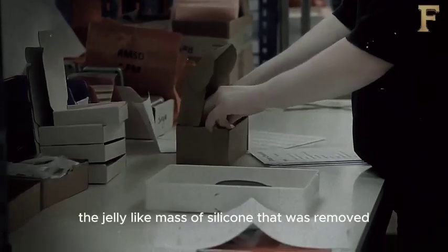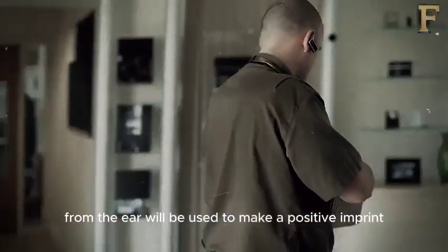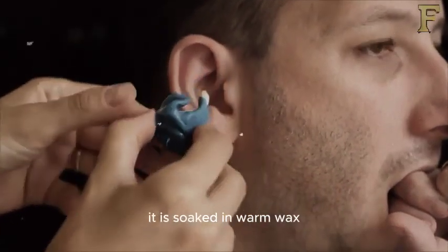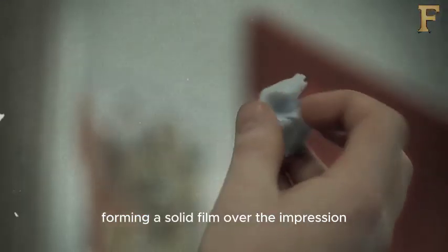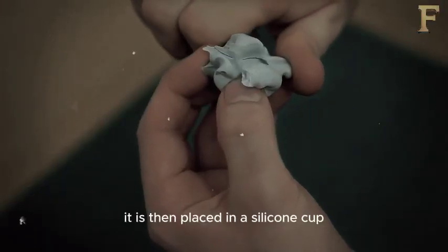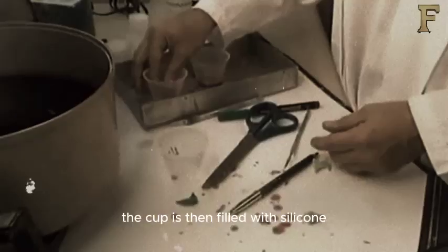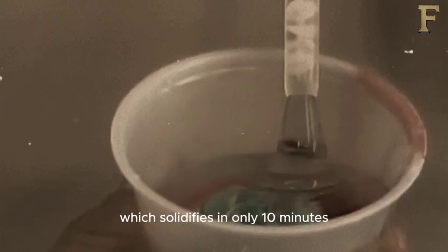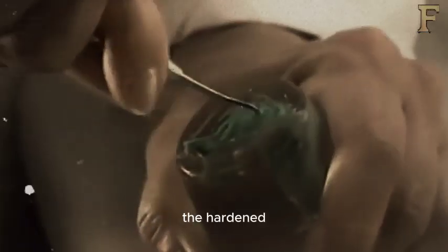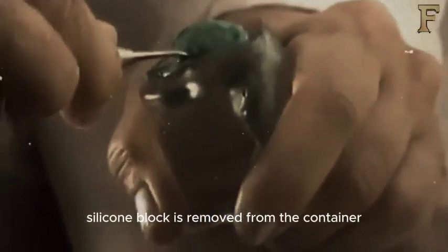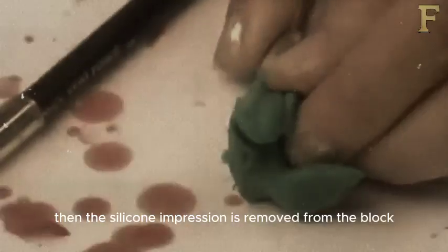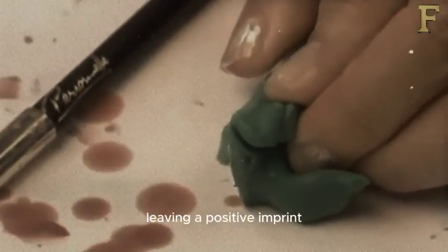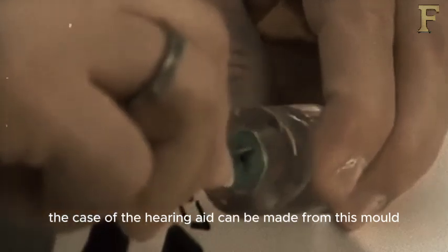The jelly-like mass of silicone that was removed from the ear will be used to make a positive imprint. It is soaked in warm wax, forming a solid film over the impression. It is then placed in a silicone cup. The cup is then filled with silicone, which solidifies in only 10 minutes. The hardened silicone block is removed from the container. Then the silicone impression is removed from the block, leaving a positive imprint. The case of the hearing aid can be made from this mold.